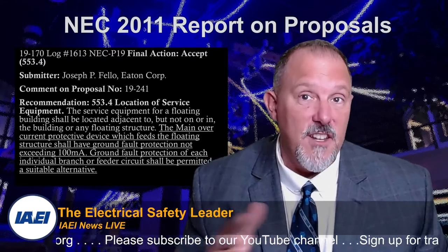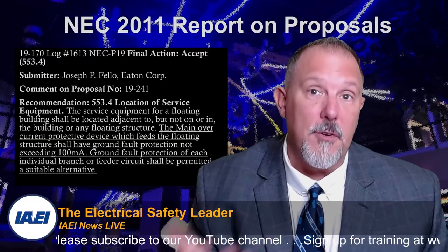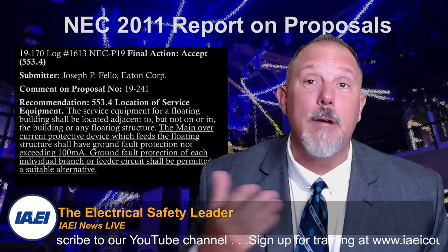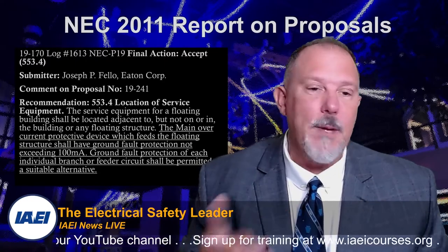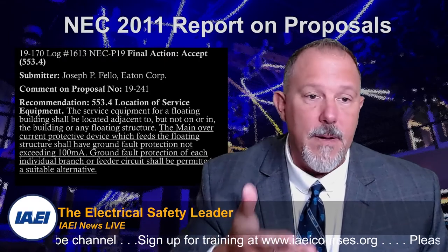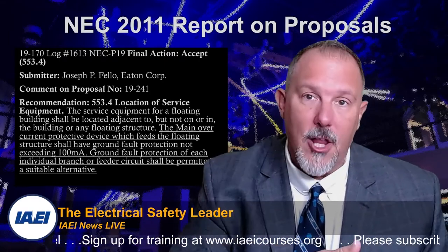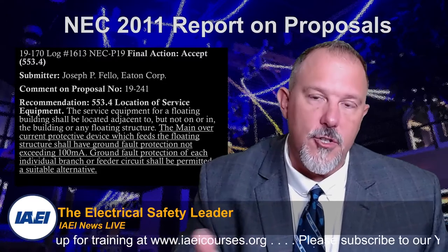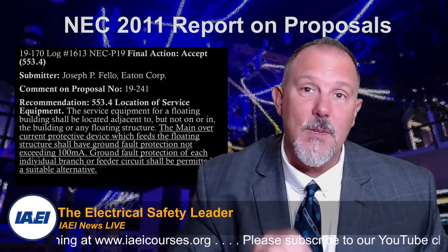30 milliamp GFPE would work, and we all know there are 30 milliamp GFPE devices readily available on the market. There were relays that would go up to 100 milliamps and beyond, and lower, that could be used, and shunt tripping circuit breakers. So product was available on the market.